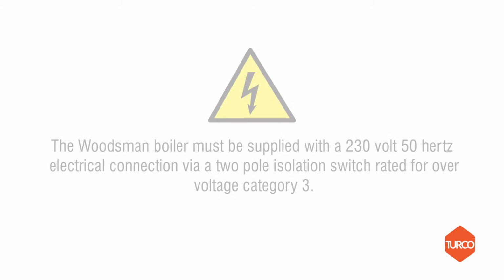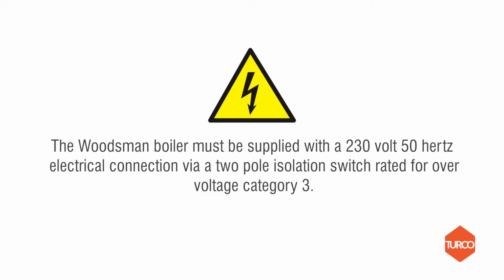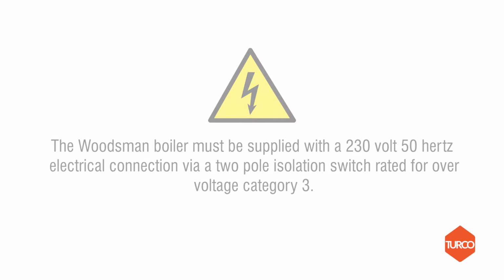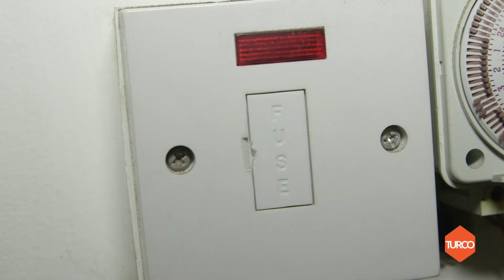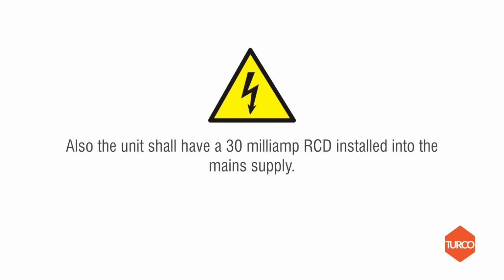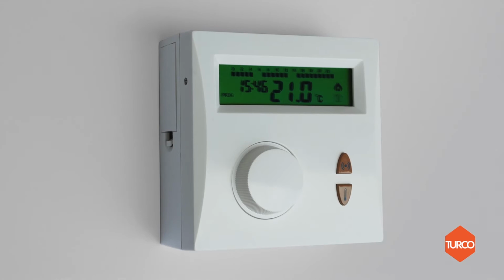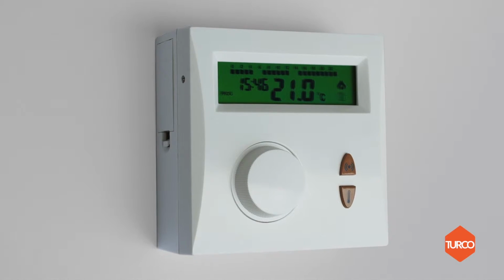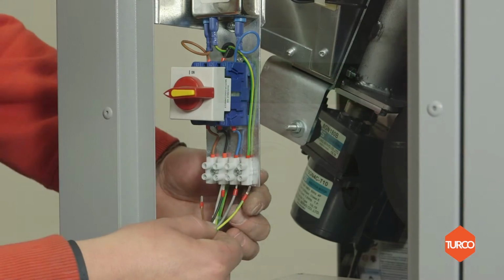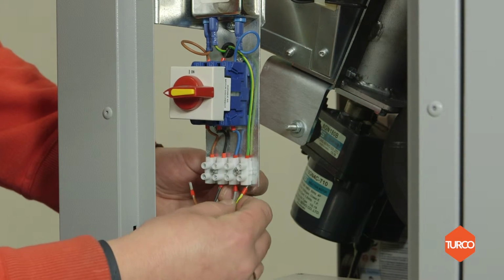The Woodsman boiler must be supplied with a 230 volt 50 Hz electrical connection via a 2-pole isolation switch rated for over voltage category 3. It must be protected with a 6 amp circuit breaker. Also, the unit shall have a 30 mA RCD installed into the main supply. Room thermostat shall be supplied controlled by extra low safety voltage. A 4-core cable needs to be connected to the boiler.